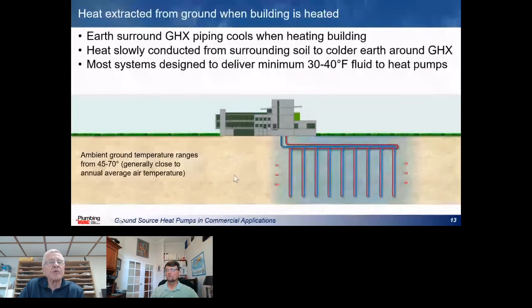The opposite happens in the winter when you're extracting heat from the dirt. You've got the same base temperature to start with. When you're starting up the system basically in fall time to heat the building, you're going to have warmer temperatures to start with because of all the heat that you've dumped in there all summer long. By the end of the winter, you're going to get down to about 30 to 40 degrees Fahrenheit. And again, that's where heat pumps are comfortable operating at. If you drop it down to 20 or 15 degrees Fahrenheit, the heat pumps are going to quit working. So the key is designing the system, the ground heat exchanger, so that it's going to provide those temperatures throughout the year.